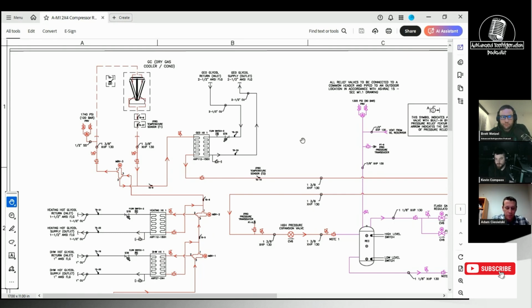The drop leg temperature, on the other hand, is not, right? Assuming that it's located in the rack or close to the gas cooler outlet temperature, there's going to be a thermal lag there. You've got piping conductive resistance for the temperature to actually see. And so the response time on temperature is much slower than pressure.